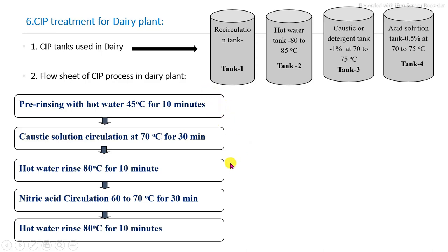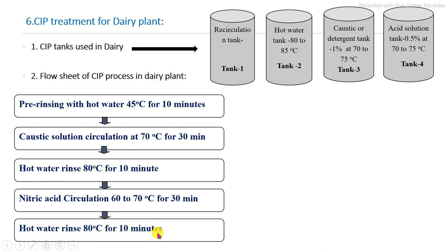In the typical dairy CIP sequence: first is pre-rinsing with hot water at 45 degrees Celsius for 10 minutes; then caustic solution circulation at 1 percent concentration at 70 degrees Celsius for 30 minutes; then intermediate hot water rinsing at 80 degrees for 10 minutes; then acid solution circulation at 0.5 percent nitric acid at 60 to 70 degrees Celsius for 30 minutes. Note that this acid solution circulation is not carried out each and every batch — it is done after every four to five batches as needed. Finally, a final water rinsing at 80 degrees for 10 minutes completes the sequence.